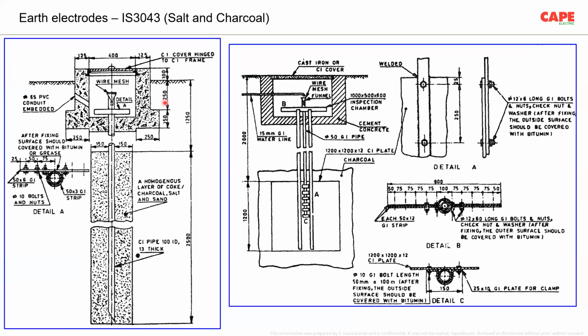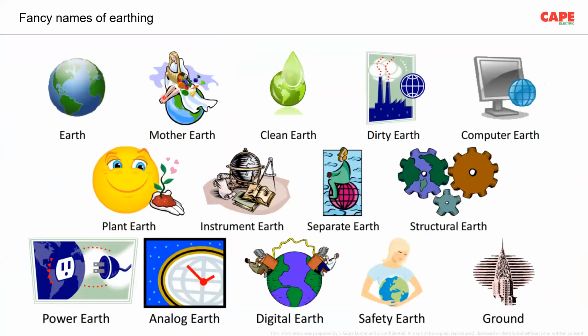I am so sorry to say that these pictures are only giving a typical example of making an earth electrode in soil. Whether you need an earth electrode in soil or not is explained in the standard, and most probably in a TN system, earth electrodes are not mandatory. In TT, of course, yes, we will see it later. As a result of these pictures from the IS standard, which is a very old standard, from the 1960s or 1970s, invention started.